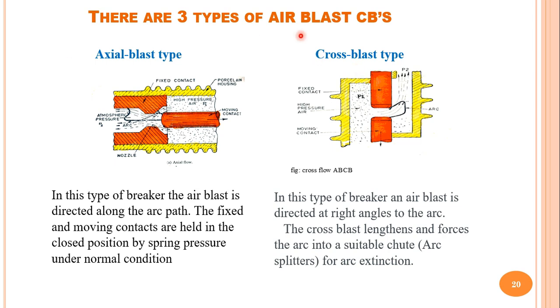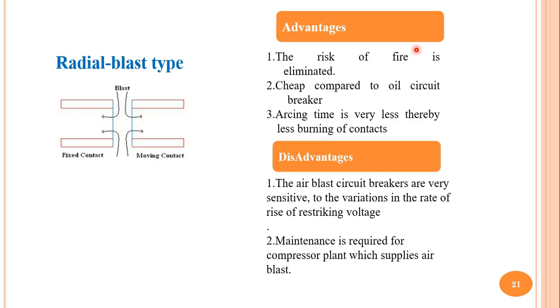There are mainly three types of air blast circuit breakers: axial blast, cross blast, and radial blast. In axial blast type, air flow is along the path of the ionized particles (the arc). Fixed and moving contacts are held in the closed position by spring pressure under normal conditions, released during faulty conditions. In cross blast type, air blast is directed at right angles to the arc path, lengthening and forcing the arc into a suitable chute for arc extinction. Radial blast combines the movement of both axial and cross flow of air.